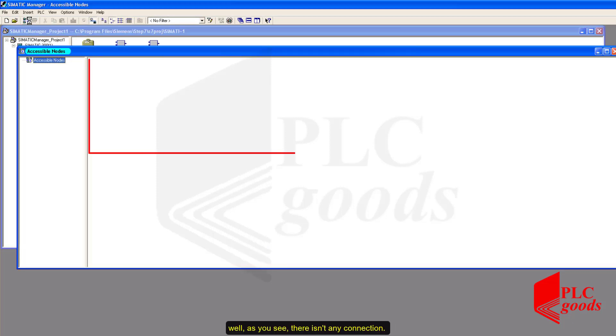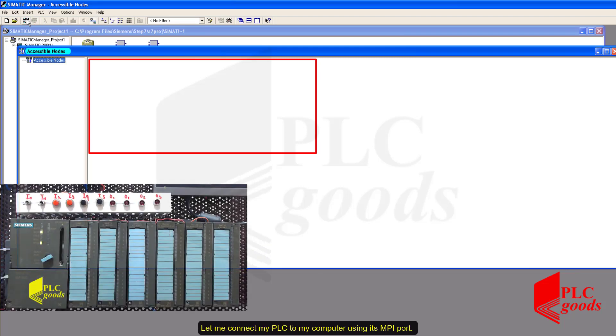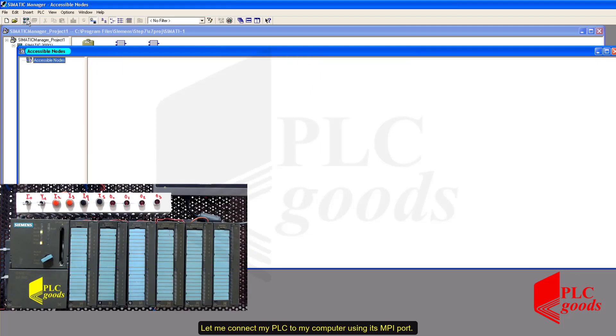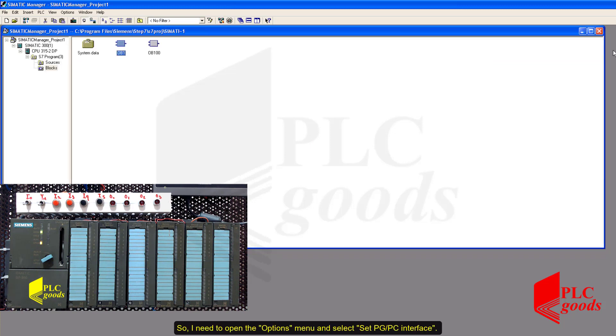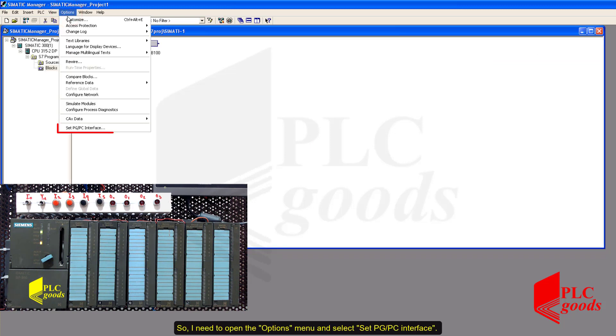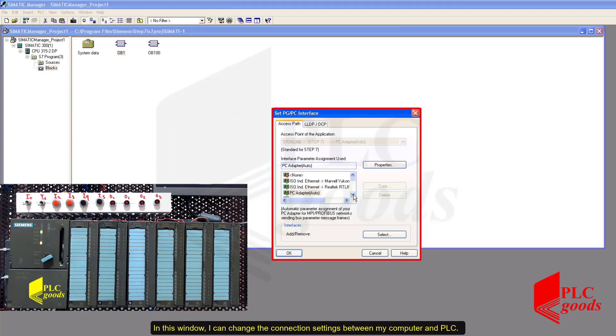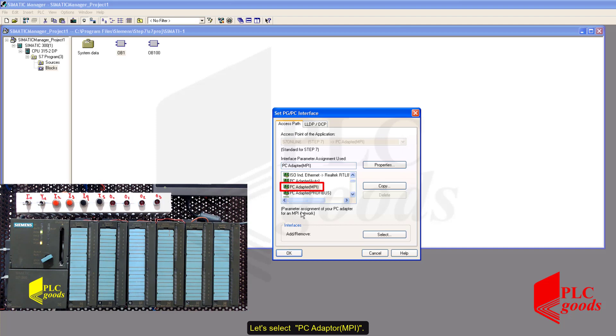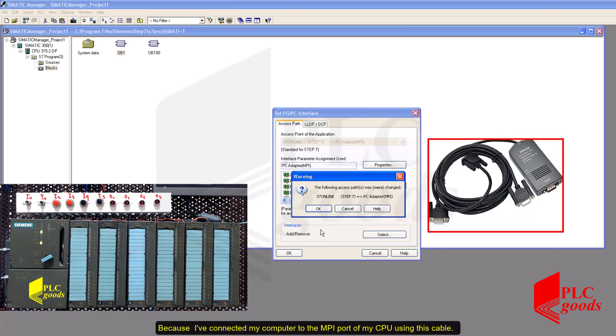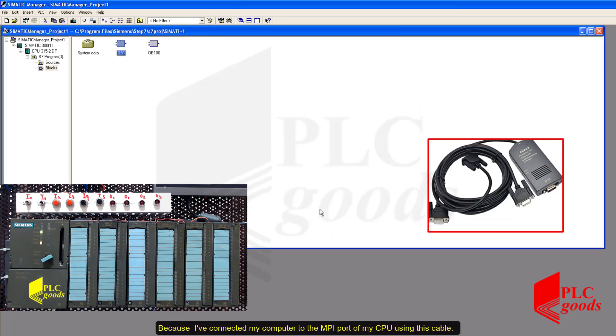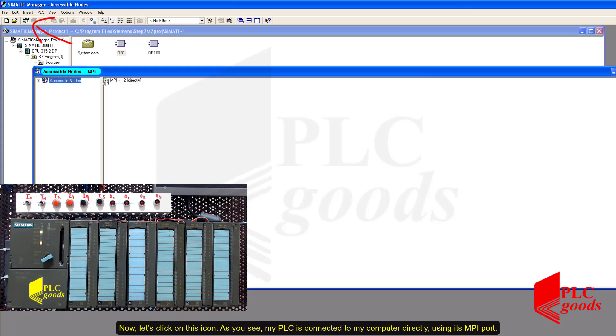As you see, there isn't any connection. Let me connect my PLC to my computer using its MPI port. I need to open the Options menu and select 'Set PGPC Interface'. In this window, I can change the connection settings between my computer and PLC. Let's select PC Adapter MPI, because I connected my computer to the MPI port of my CPU using this cable. Now let me click on this icon. As you see, my PLC is connected to my computer directly using its MPI port.